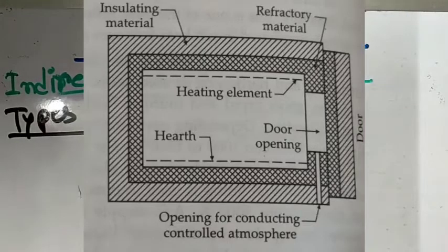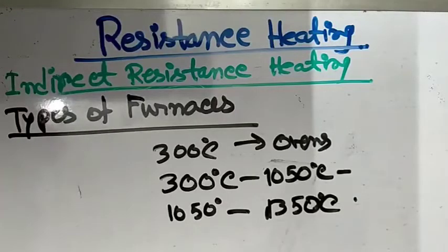Now, resistance heating using a metallic resistor, widely used for a controlled atmosphere, is shown by this figure. Resistance heating, usually with metallic resistors, is widely used for heat treatment, but the temperatures attainable with metallic resistors are not high enough for melting most non-ferrous metals and cast iron. Graphite can, however, be used at much higher temperatures.